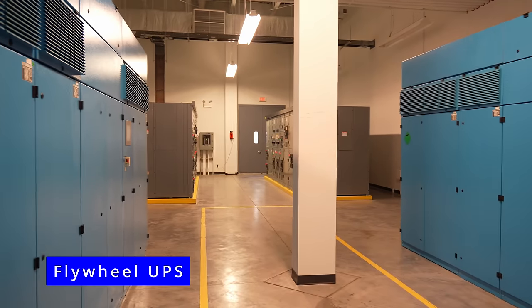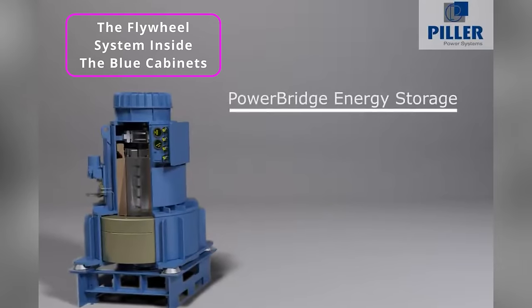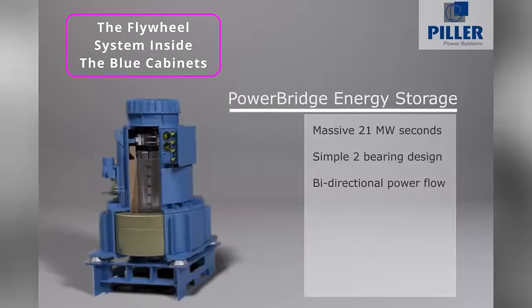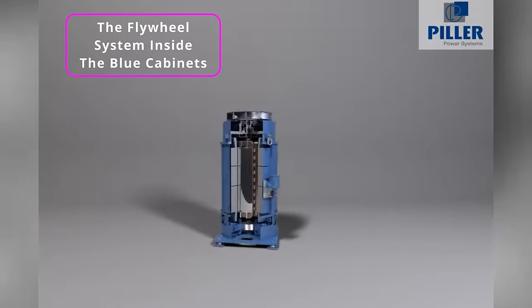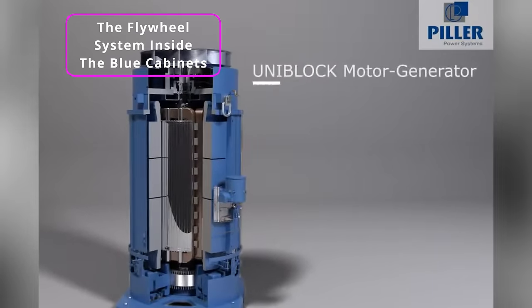The answer is 16 seconds — that's the amount of time it takes for one of the generators to go from off to full speed, like a semi rig doing a quarter mile in about 16 seconds. Inside the UPS there's a large rotating drum that is magnetically levitated with very little friction in a hermetically sealed container. When the power goes out, the resistance of the motor windings slows that container down as it generates power. When the generators kick on, those same motor windings become a motor and spin it back up.